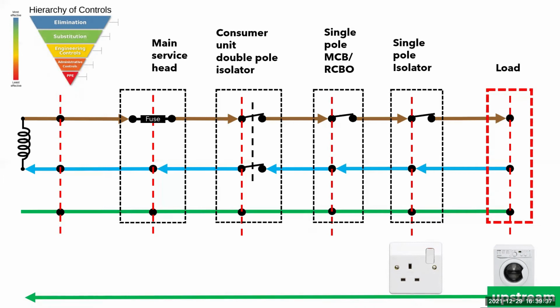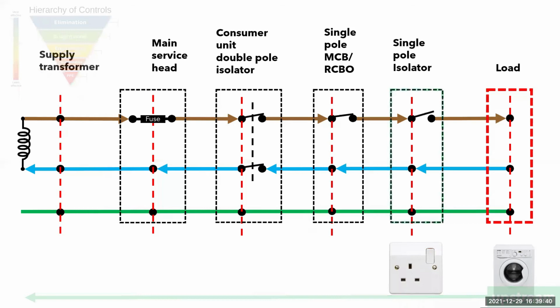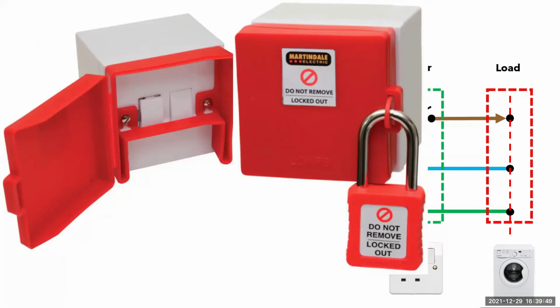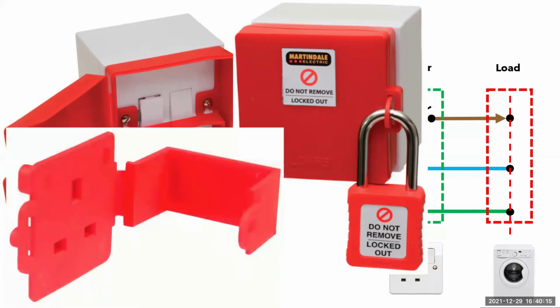We could be thinking that isolating the switch would be sufficient, as this would remove the electrical supply. But what would be stopping someone from operating the switch whilst we were working on the appliance? And it's worth noting that a switch on a socket is not capable of being locked off. So the best option is to unplug the appliance. What's to stop people plugging in the appliance, I hear you cry? Well, that's a good question. Fortunately, there is an affordable piece of equipment from Martindale on the market for such dilemmas, and it's one of these. They also sell one for the appliance itself, and so does Master Lock.